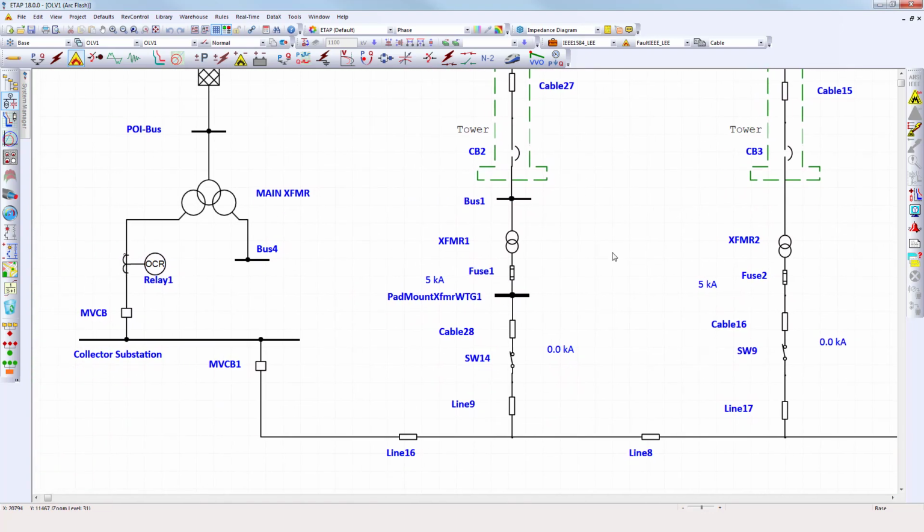And with this step-up transformer, which I'm highlighting currently, we'll have both a primary side and a secondary side at the low voltage of the wind turbine. Of course, as I mentioned during the previous slides, we're focusing on the 34.5 kV collector system. So first, we'll perform an arc flash using the theoretically derived Lee method to observe the energy that we get for a fault at that location. So we'll proceed to place a fault insertion on that location.